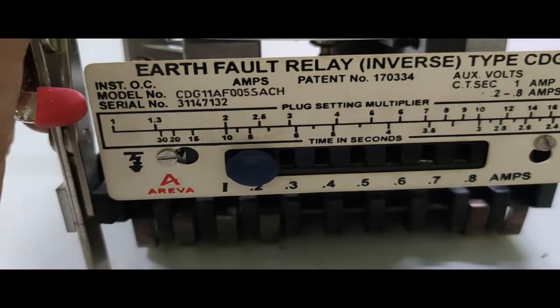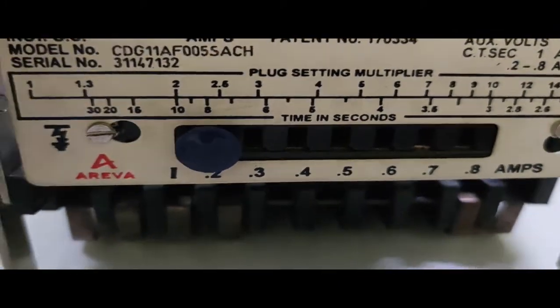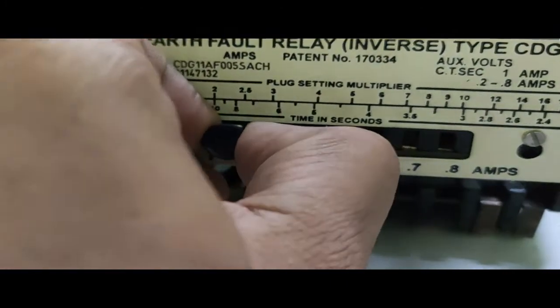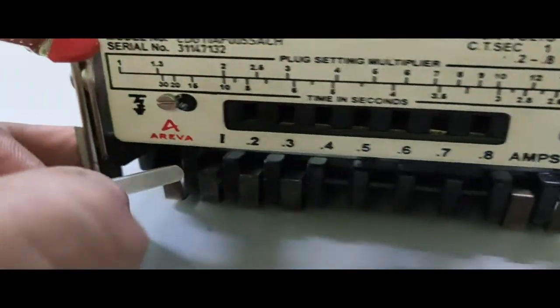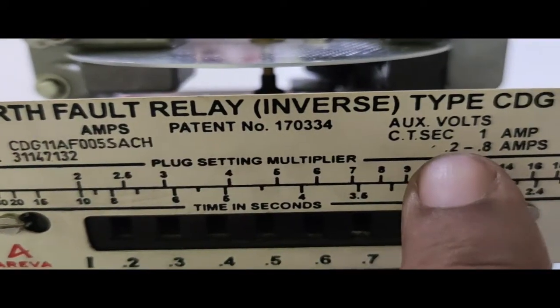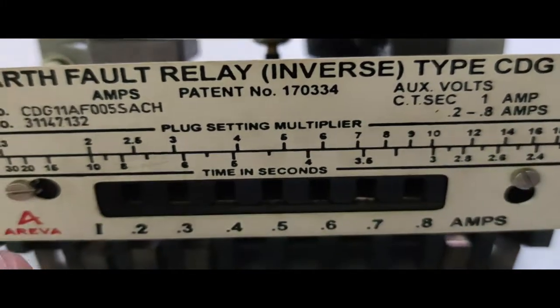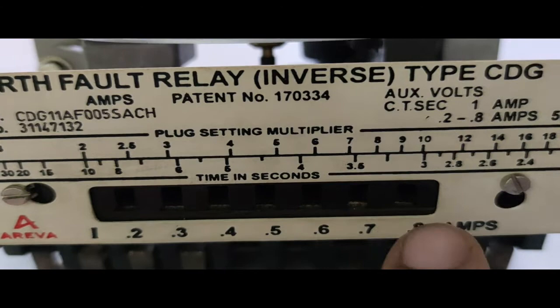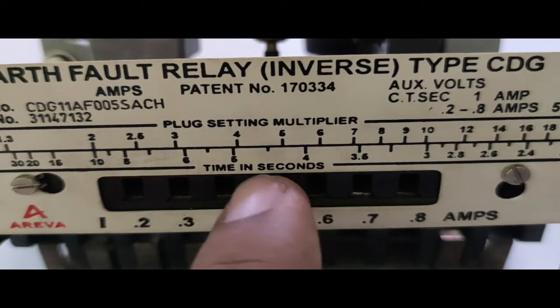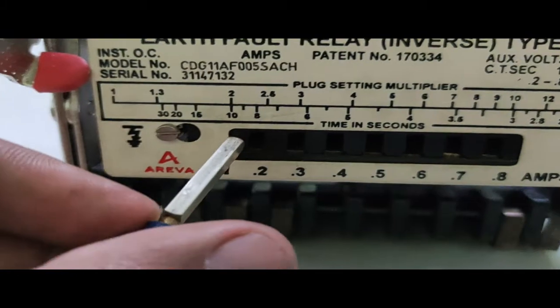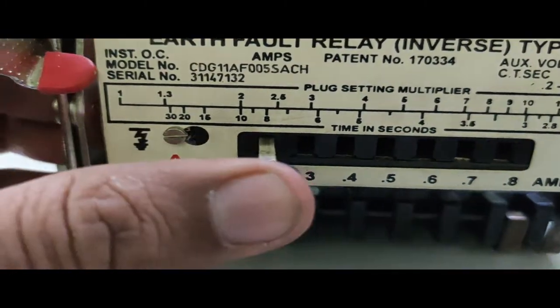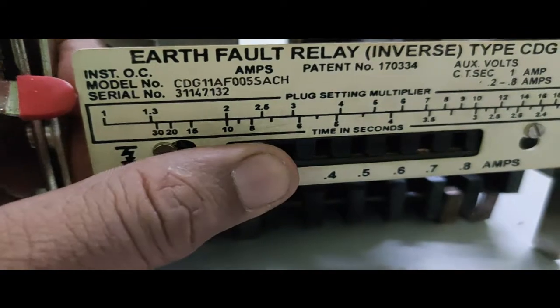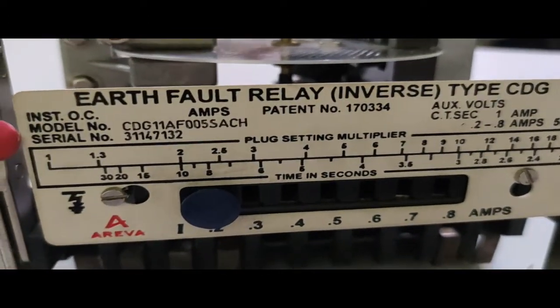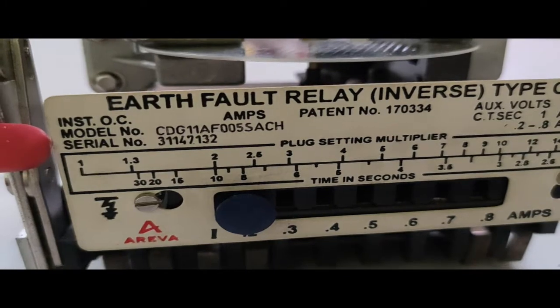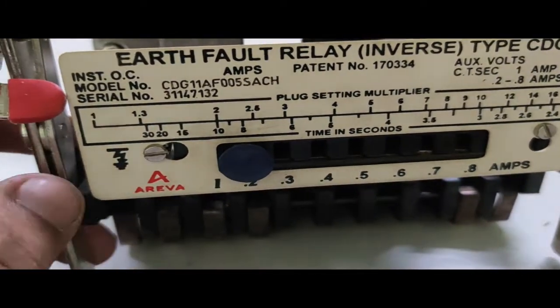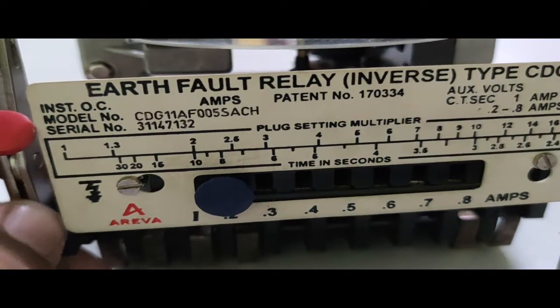Now this is called the plug setting of the relay. Here you see some small holes, and just below the holes some current rating is written. As it is mentioned, the relay can be operated from 0.2 to 0.8 ampere, so here you see 0.2, 0.3 up to 0.8 ampere. This is the relay operating current. If I short circuit this one, 0.2, that means 0.2 ampere is now connected to the relay as the relay operating current. So if the current through the relay goes beyond 0.2 ampere, then the relay should operate.